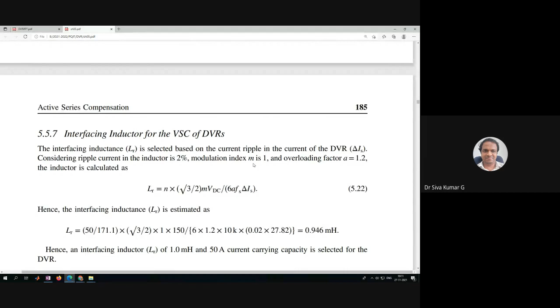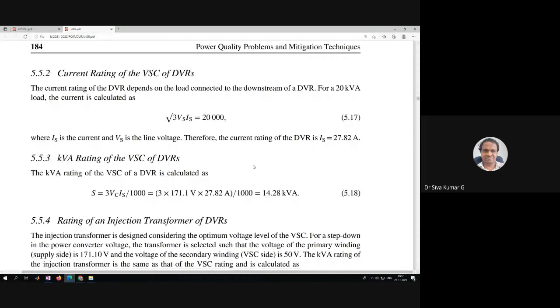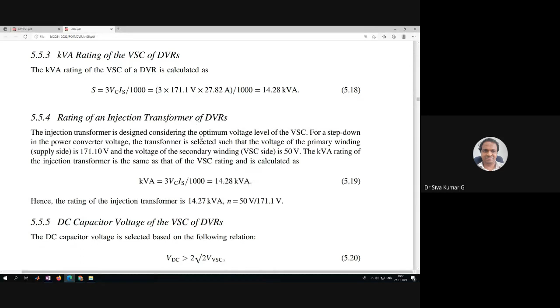Up to here, we have seen the current rating of the voltage source converter, the voltage rating of the VSC of a DVR, the KVA rating of the voltage source converter of a DVR, and the rating of an injection transformer of a DVR, and then the DC capacitor voltage. Generally they can keep it around two times, or root two times, of the VSC value. Two into root two times is a much higher voltage.